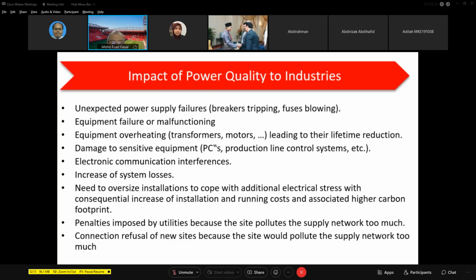So with unexpected power supply failures, circuit breakers will trip, fuses will blow, and some equipment will malfunction. In some cases, like I mentioned just now, in Malacca, we have cases of customer transformer overheating and tripping because of the harmonic issue. And sensitive equipment is quite critical because most control systems are semiconductor or electronic based. They are very prone to lightning. And then communication interference is also an issue. And harmonics cause I squared R losses, because as I increases, losses increase.